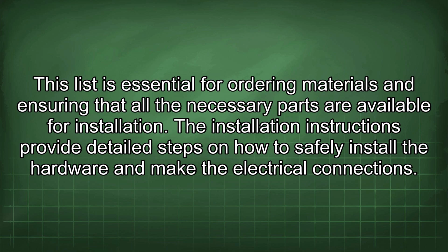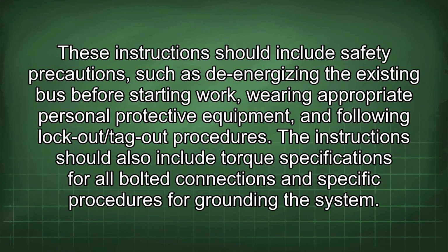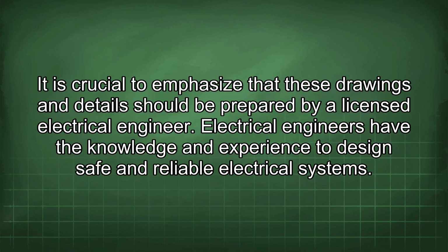The installation instructions provide detailed steps on how to safely install the hardware and make the electrical connections. These instructions should include safety precautions such as de-energizing the existing bus before starting work, wearing appropriate personal protective equipment, and following lockout/tagout procedures. The instructions should also include torque specifications for all bolted connections and specific procedures for grounding the system. It is crucial to emphasize that these drawings and details should be prepared by a licensed electrical engineer.